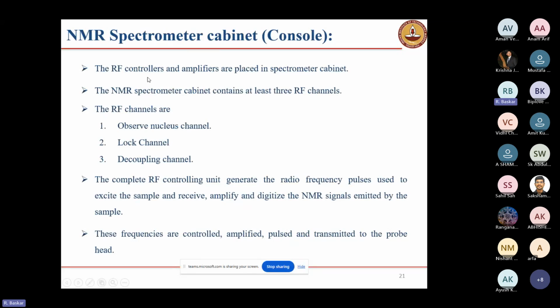The radio frequency controllers and amplifiers are available in this NMR cabinet. The complete radio frequency controlling unit generates the radio frequency pulses used to excite the sample, and receives, amplifies and digitizes the signals emitted by the sample. In the radio frequency channel, generally three coils are available. One is the observe channel, another is the lock channel, that is the deuterium coil, and the third is the decoupling channel. In general this is for two channel instruments. If we have three channels, one is for proton and the other two are for X nucleus. With two channel instruments, at maximum we can do 2D experiments.